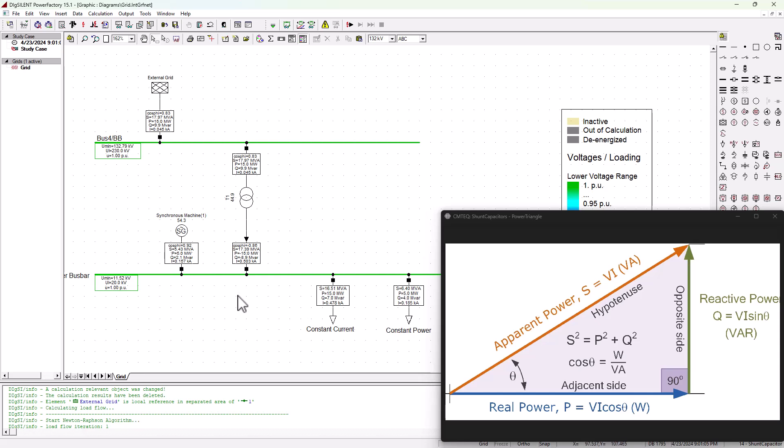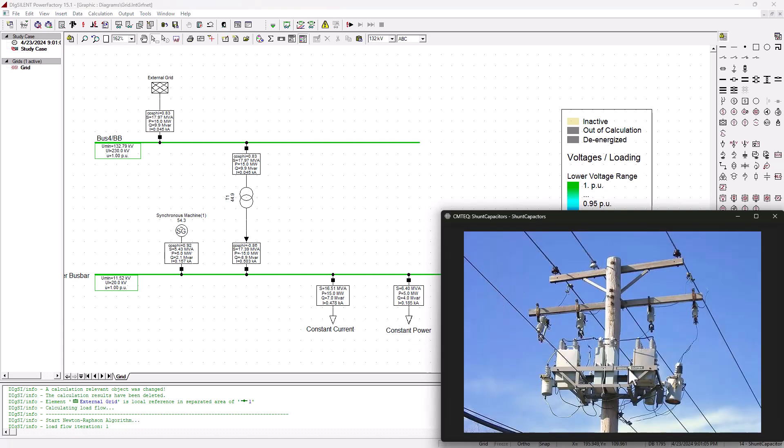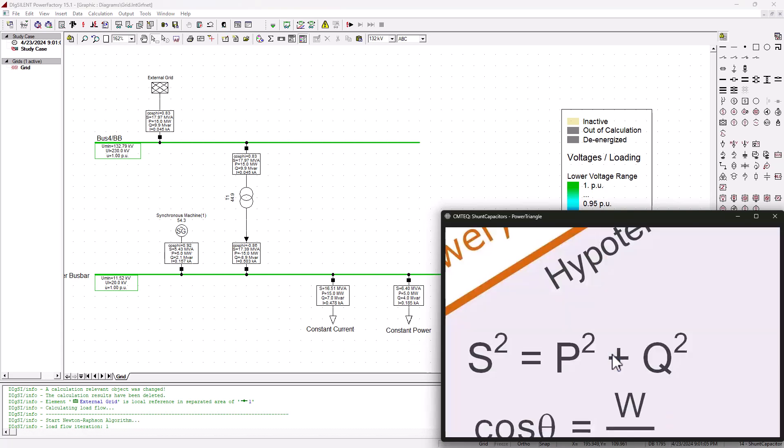Now we can do an adjustment here for the synchronous machine to actually support the load busbar because that is actually what it is meant to do. But right now the machine is only able to add 2.1; it cannot do more than that. Which means we are only left to adding the shunt capacitors onto our system.